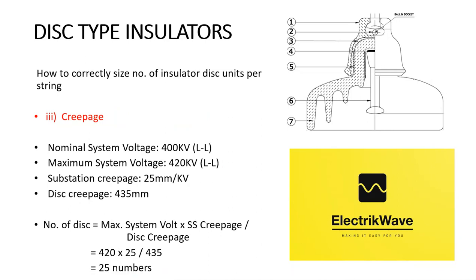Here we will calculate the number of insulator disk units per string based on creepage. Nominal system voltage is 400 kV line to line. Maximum system voltage is 420 kV line to line. Substation creepage is 25 mm per kV. Disk creepage is 435 mm. The formula: number of disks per string = maximum system voltage × substation creepage / disk creepage. This gives a requirement of 25 disks per string.